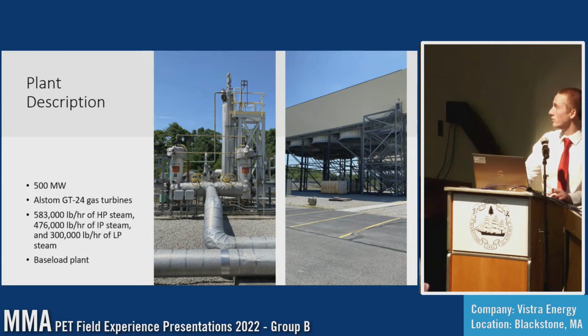Each unit runs a GT24 gas turbine, with the HRSG capable of 583,000 pounds per hour of HP steam, 476,000 of IP steam, and 300,000 of LP steam. They were on a single shaft alignment, which is a very European design from my understanding, and a lot about the plant was very European in nature.